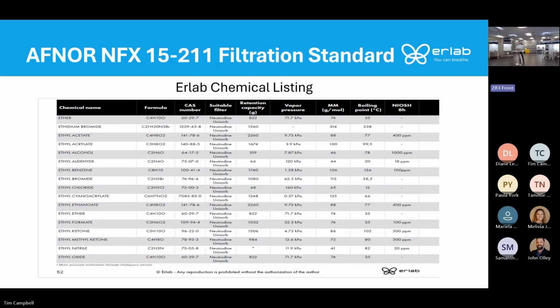This is a filtration standard that was designed back in 2009, and it's the strictest filtration standard in the world. But this chemical listing gives us the ability to then test or analyze what you're going to use in the hood before that. So this chemical listing shows the retention capacity in grams. You can see ethyl acetate is on there. That's a good substitute for dichloromethane. It's about a 2,200 gram retention capacity. It's almost 2,000 more than dichloromethane itself.